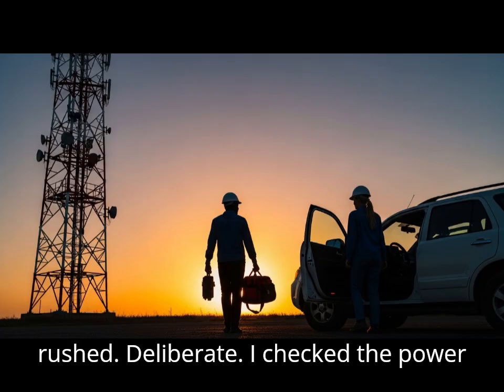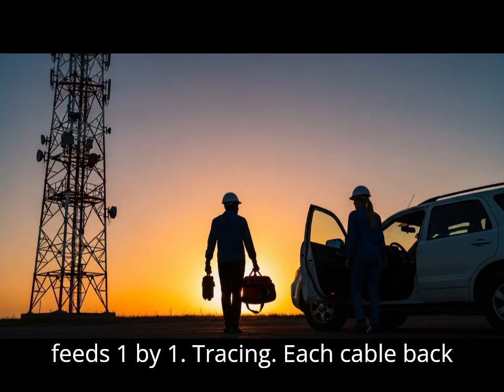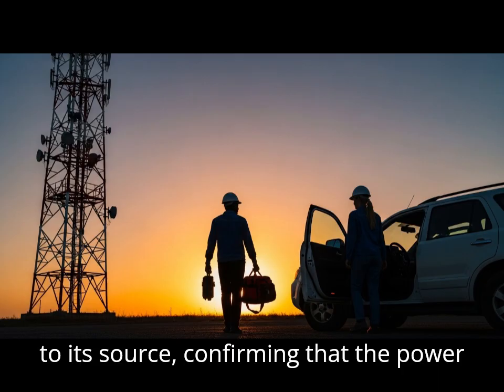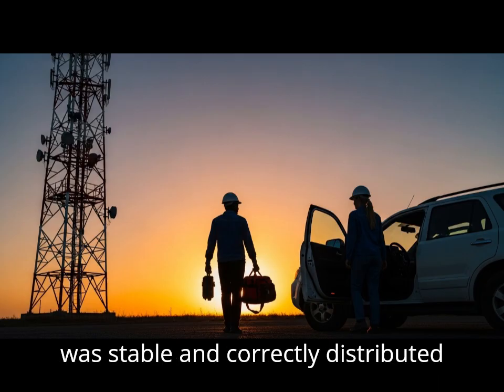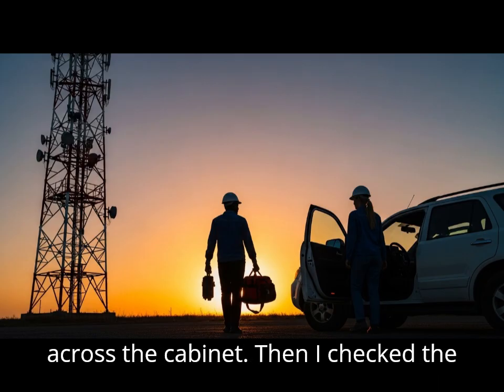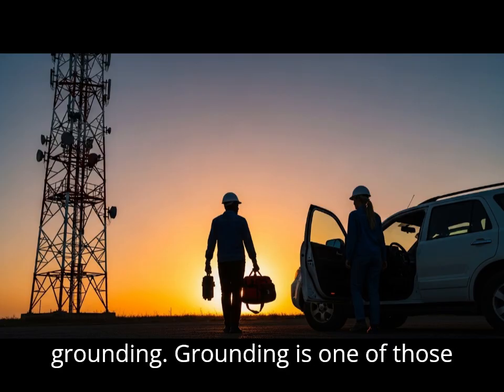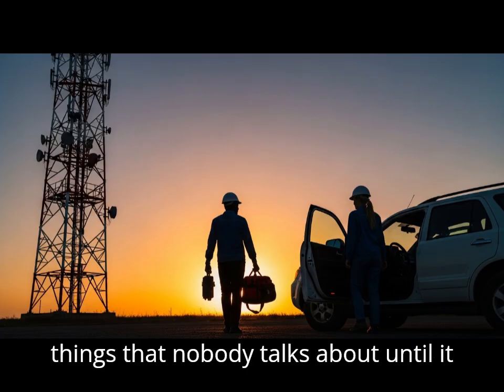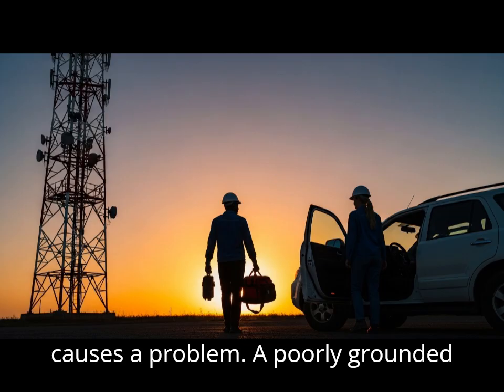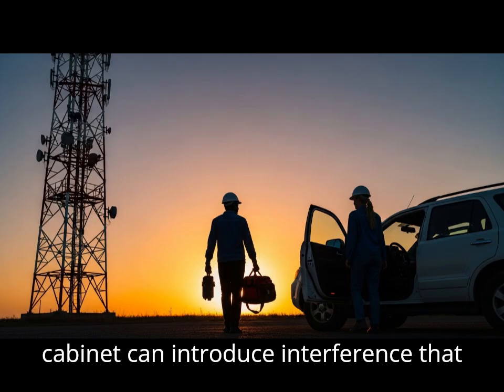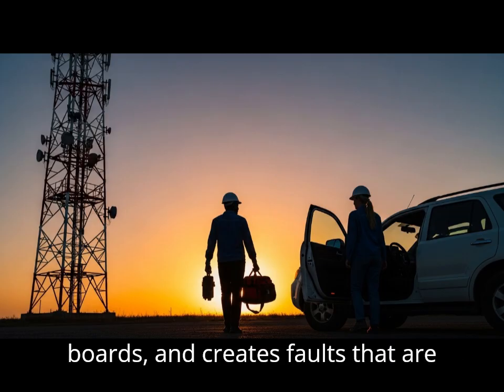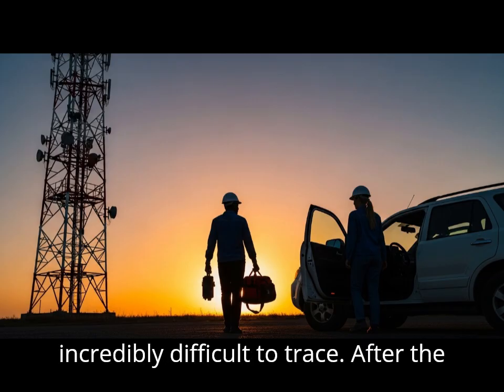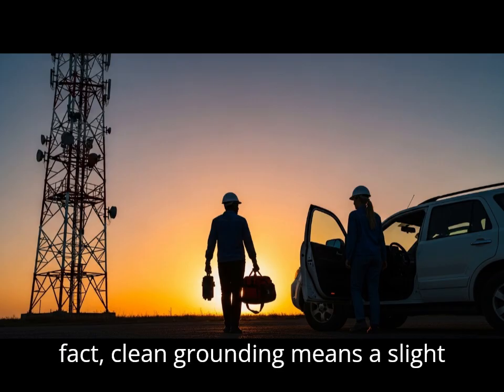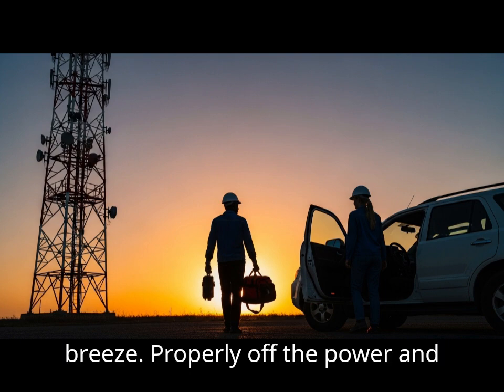I checked the power feeds one by one, tracing each cable back to its source, confirming that the power was stable and correctly distributed across the cabinet. Then I checked the grounding. Grounding is one of those things that nobody talks about until it causes a problem. A poorly grounded cabinet can introduce interference that corrupts signals, damages sensitive boards, and creates faults that are incredibly difficult to trace after the fact. Clean grounding means the site breathes properly.